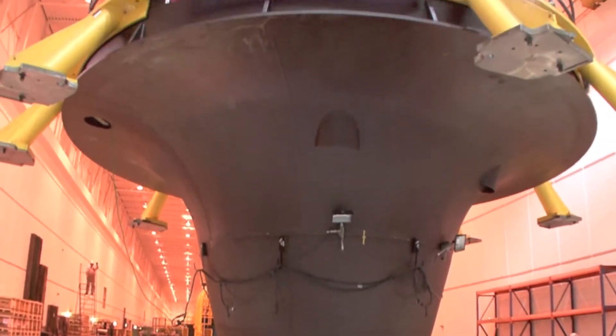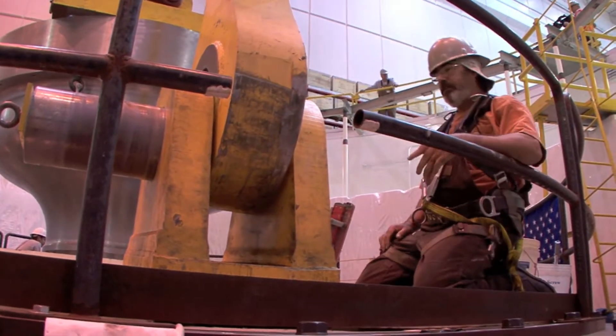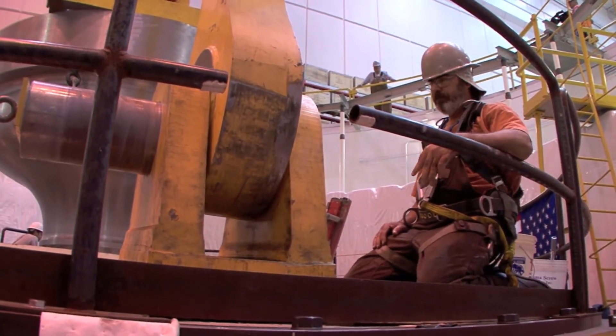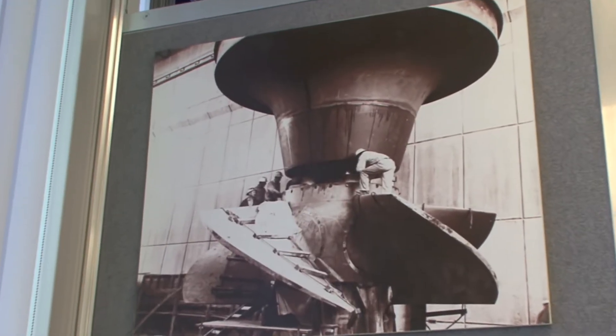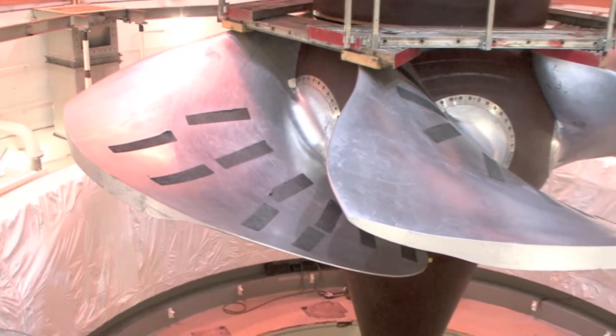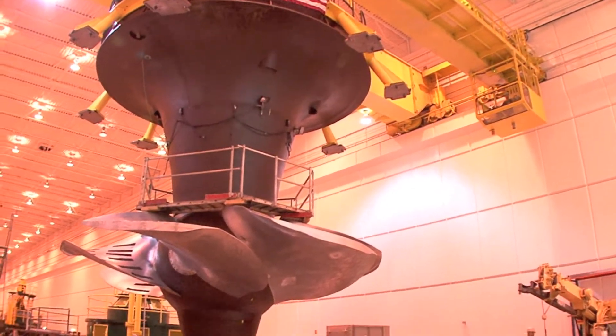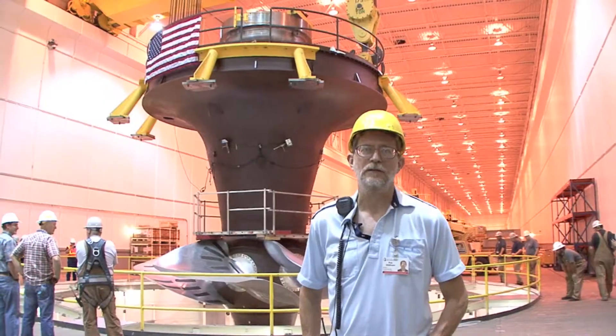We started in 2004. This is our last turbine — tenth of ten. The original turbines were 120,000 horsepower. These are 150,000 horsepower, so we get additional output, plus efficiency gains of between three and five percent.